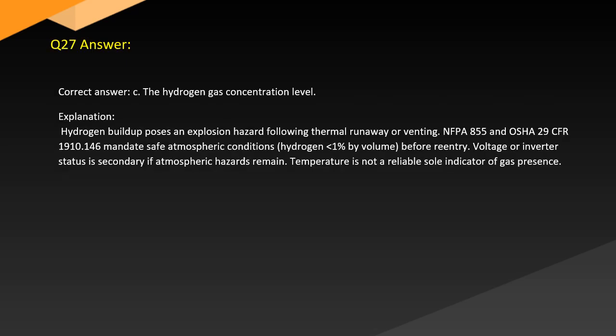Answer. Correct answer: C. The hydrogen gas concentration level. Explanation. Hydrogen buildup poses an explosion hazard following thermal runaway or venting. NFPA 855 and OSHA 29 CFR 1910.146 mandate safe atmospheric conditions, hydrogen below 1% by volume, before re-entry. Voltage or inverter status is secondary if atmospheric hazards remain. Temperature is not a reliable sole indicator of gas presence.